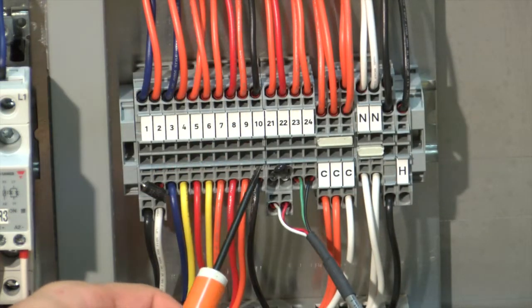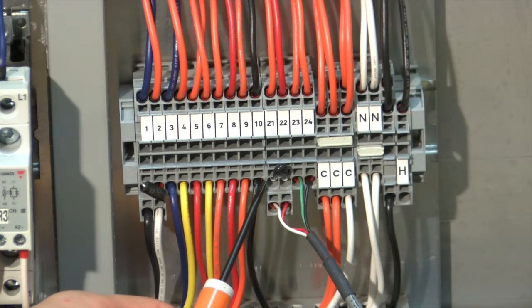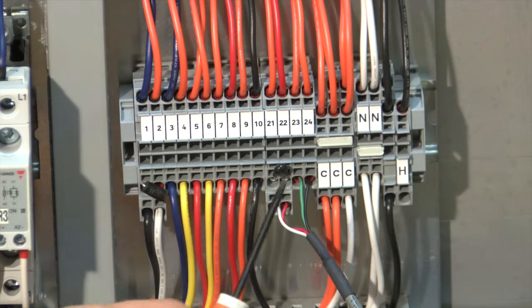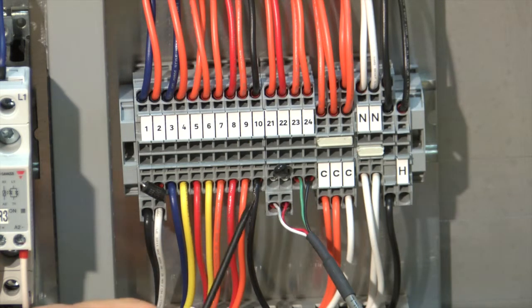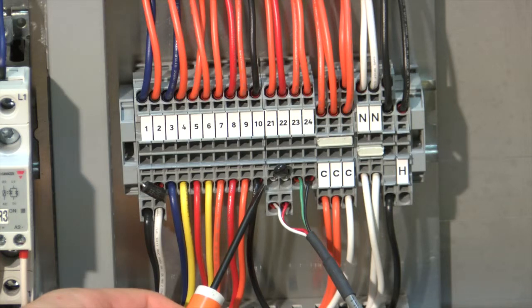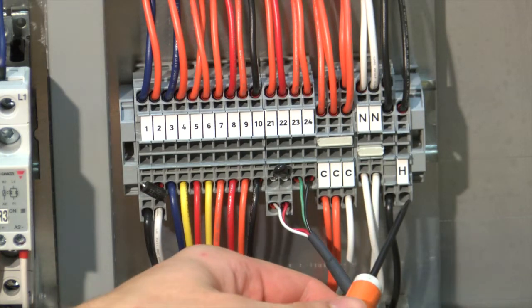Following our wiring diagram, the wire at the bottom of number 10 is the power for the fans that cycles on and off. In order to make the fans stay on continuously, we move this wire at the bottom of number 10 to the open H block all the way to the right. This will be a constant source of power that will cause the fans to run continuously and dry the chute out.